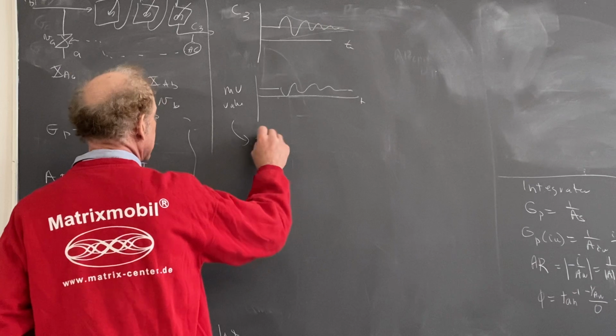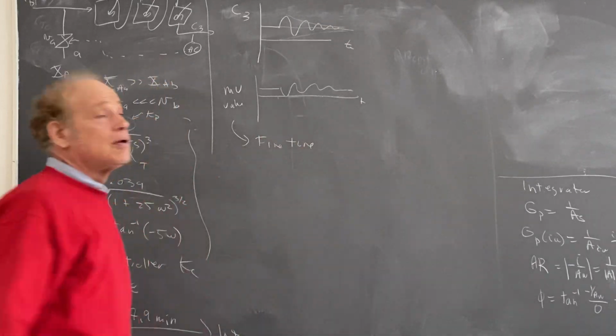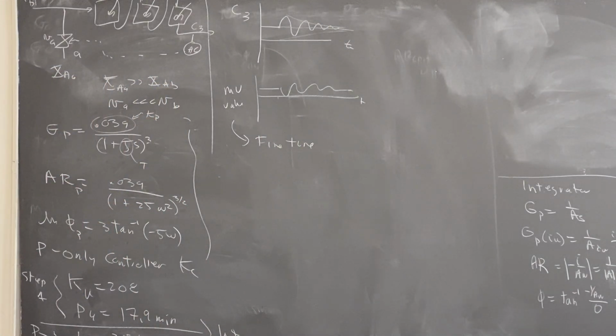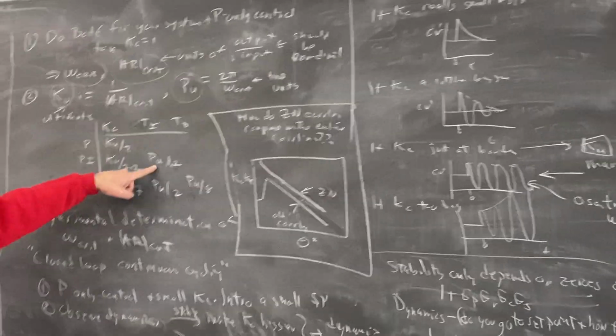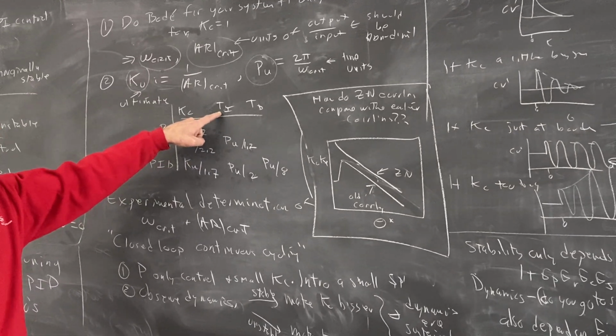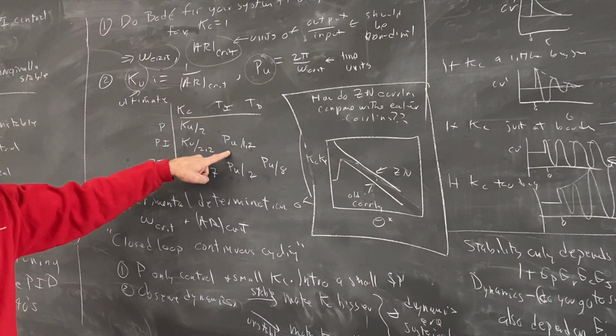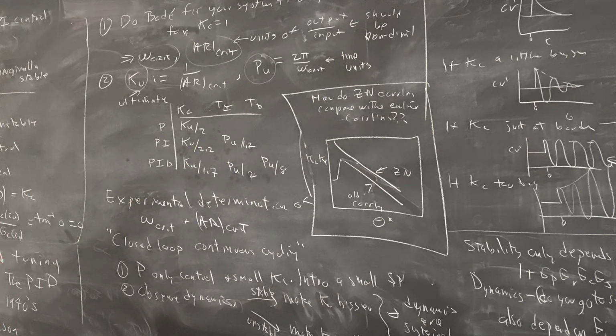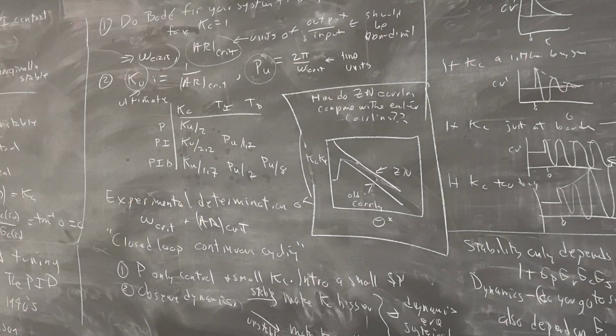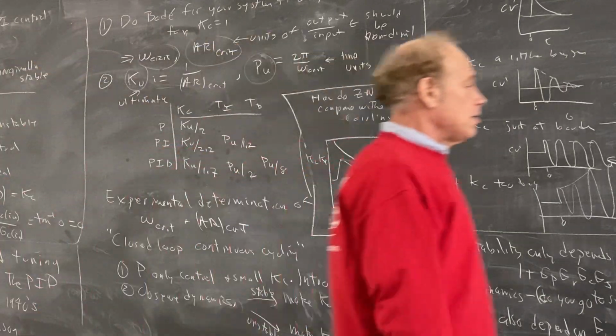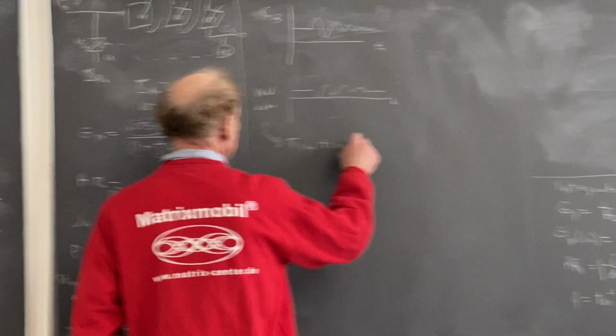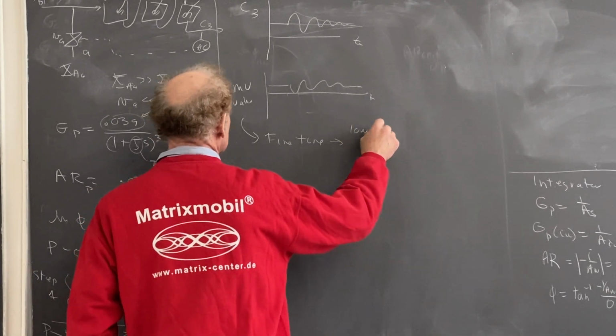Then what you would do is you would fine-tune. When you fine-tune, you would try to slightly adjust, make the system a bit more aggressive, a little higher value of K. Well, the problem is it's not going to the set point fast enough. So you would make the integral controller a little more aggressive. You make the integral controller more aggressive by shortening the time. So my initial tuning and then my fine tuning would be to lower TI.